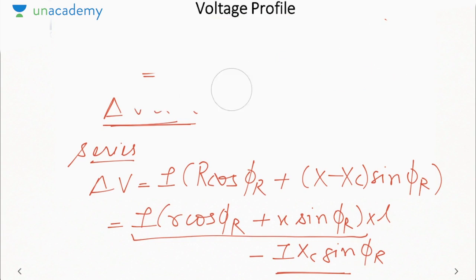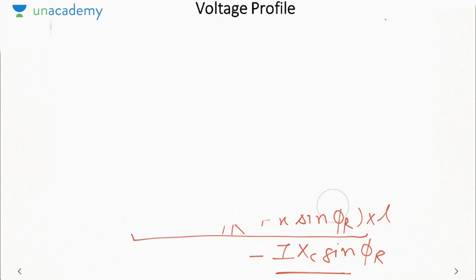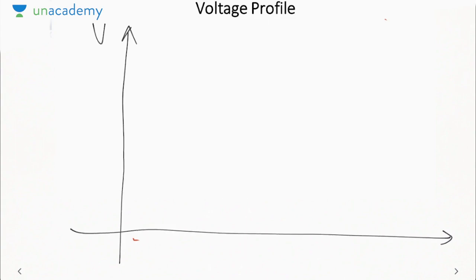Now let us plot voltage versus distance for three cases: one without compensation, one with shunt compensation, and another with series compensation. So if this is voltage, this is length. This is my sending end and this is my receiving end. Ideally voltage should have been flat, but what happens without compensation? This is my characteristics. Voltage will go on decreasing, or with increase in length, voltage drop will go on increasing. Delta V will increase with increase in length.